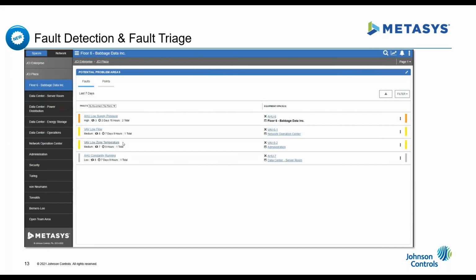So, when you have colder air being pushed out of an air handler into a zone, the zone may be reheating that air, and the zone may be perfectly satisfied, which means there's no alarm going on, but still you're heating and cooling simultaneously, which is certainly wasting energy, and more than likely exposing your equipment to runtime failures over time, because it's having to work harder to satisfy the conditions that it was set up to do design-wise without the faults occurring. So, fault detection is an extremely important part of that.